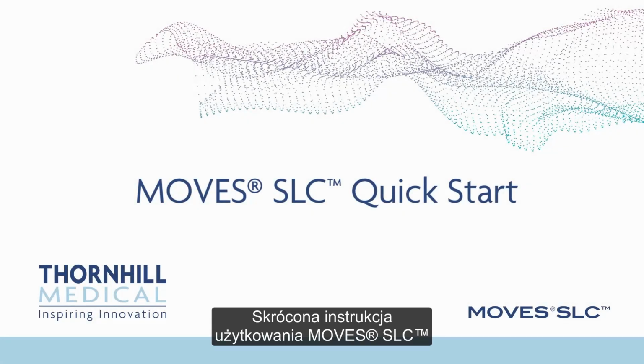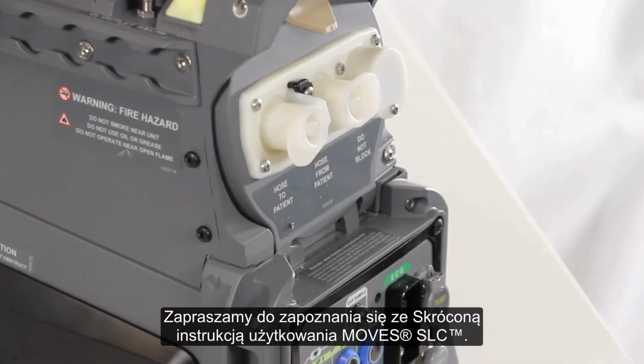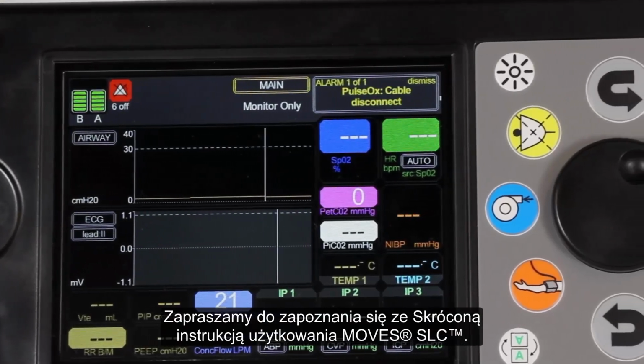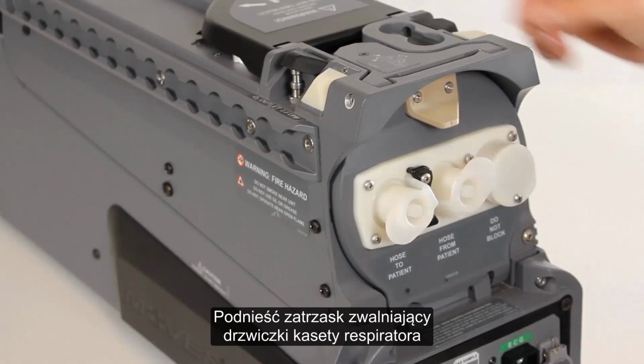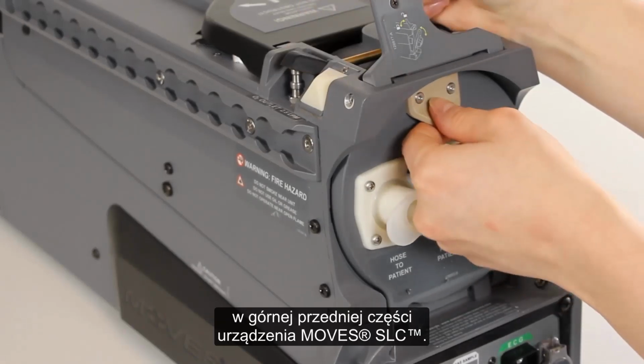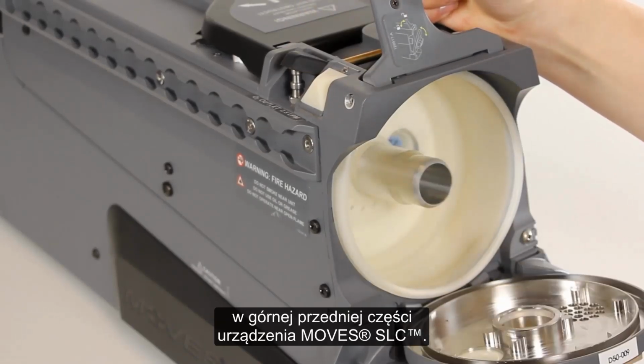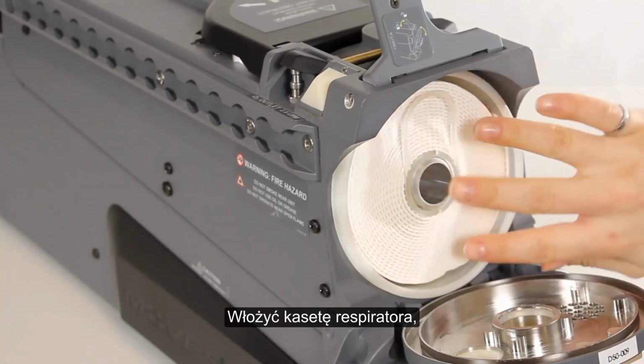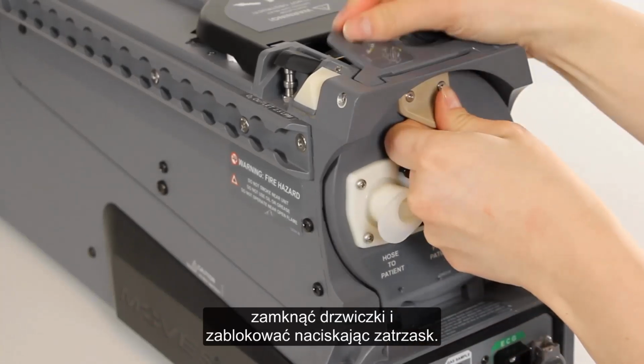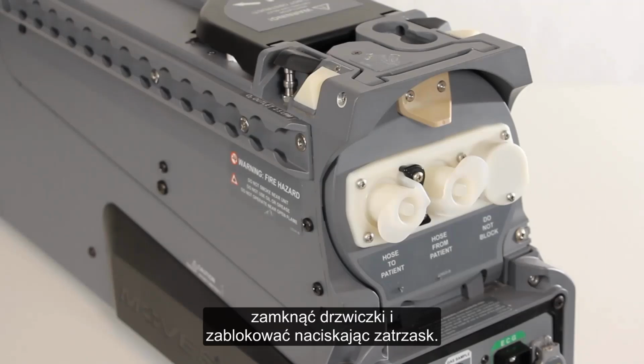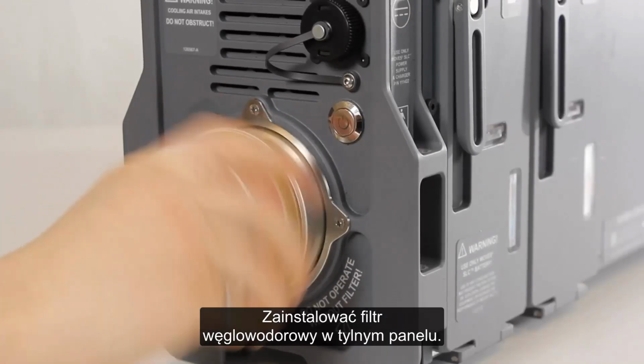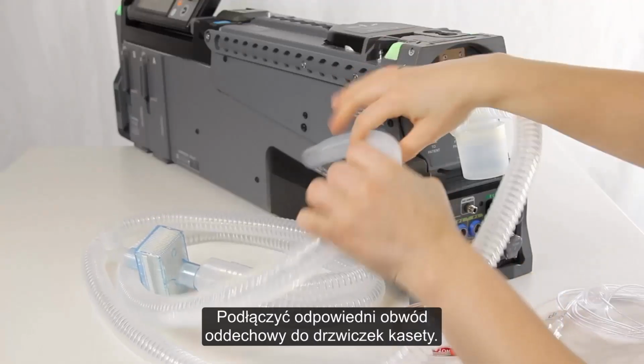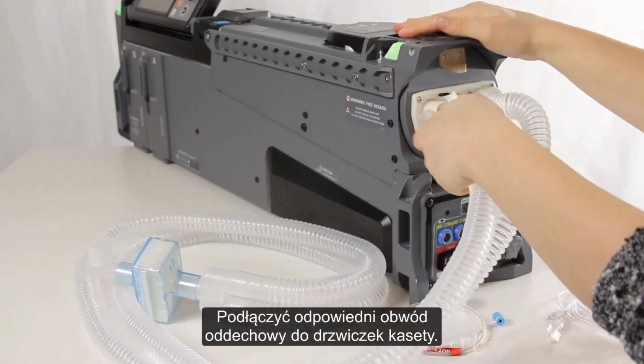Moves SLC Quick Start. Welcome to the Moves SLC Quick Start Guide. Lift the release latch for the ventilator cartridge door at the top front of the Moves SLC. Insert the ventilator cartridge, close the door, and lock it by depressing the latch. Install the hydrocarbon filter in the rear panel. Attach the appropriate breathing circuit to the cartridge door.